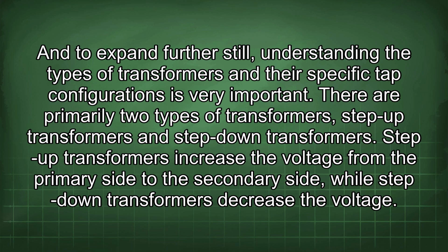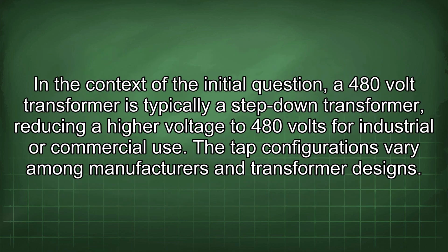There are primarily two types of transformers: step-up transformers and step-down transformers. Step-up transformers increase the voltage from the primary side to the secondary side, while step-down transformers decrease the voltage. In the context of the initial question, a 480-volt transformer is typically a step-down transformer, reducing a higher voltage to 480 volts for industrial or commercial use. The tap configurations vary among manufacturers and transformer designs.